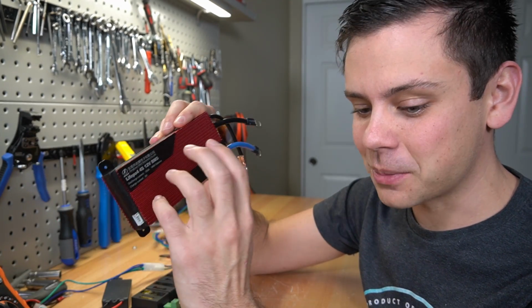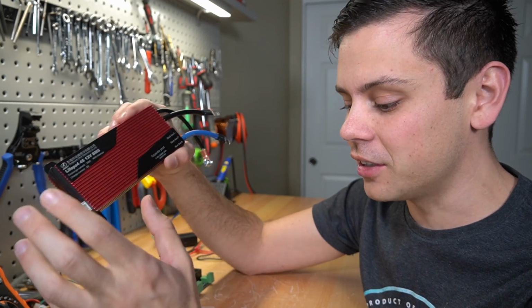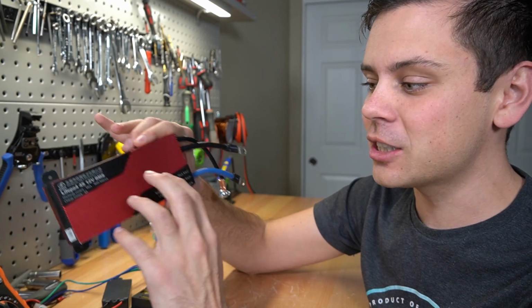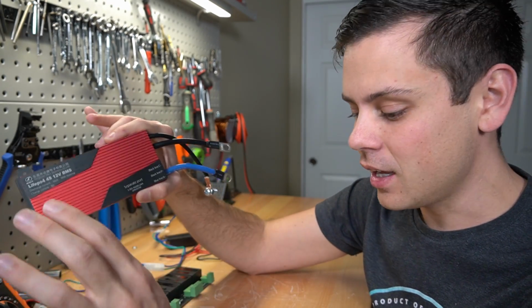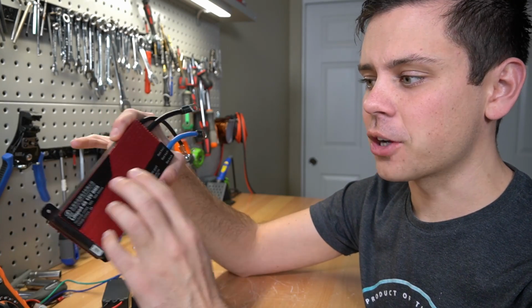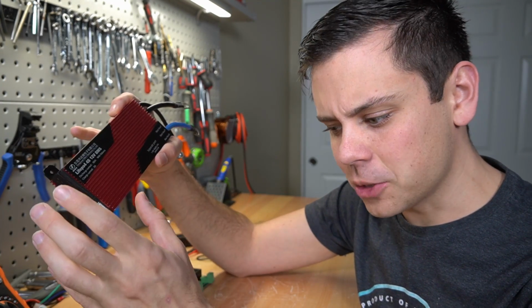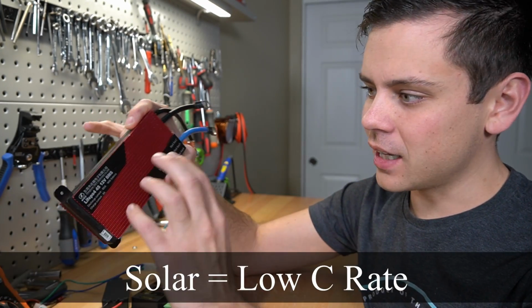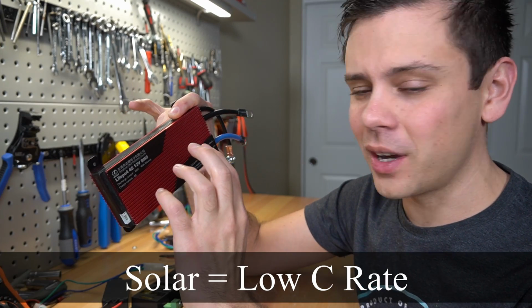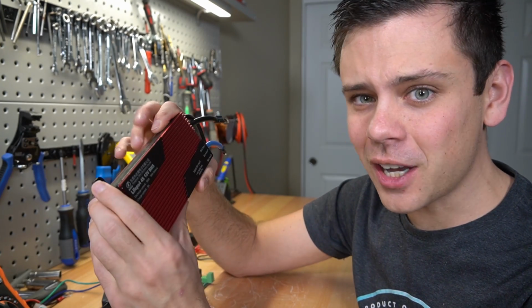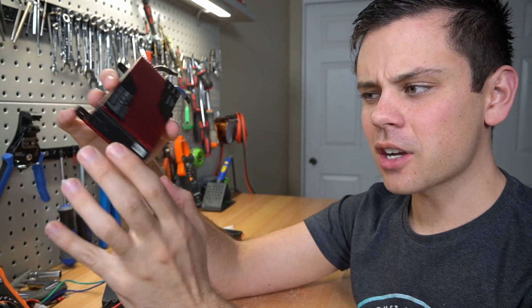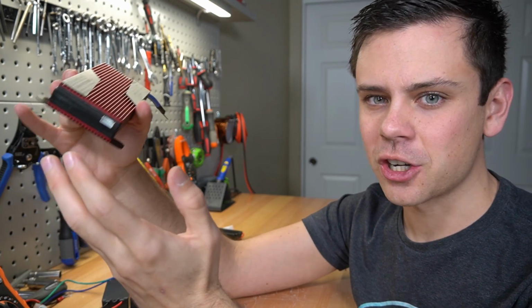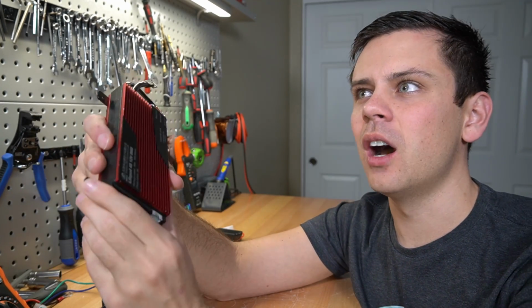These are designed for a specific application with new cells and work perfectly fine, keeping cells balanced and happy. Cells can go out of balance faster if you push the C rate, but for solar, since the BMS is typically the limiting factor current-wise, most of you will never have that problem. Another cause of imbalance is temperature extremes, and another is improper use - if a cell is damaged, you'll get faster cell drift over time.